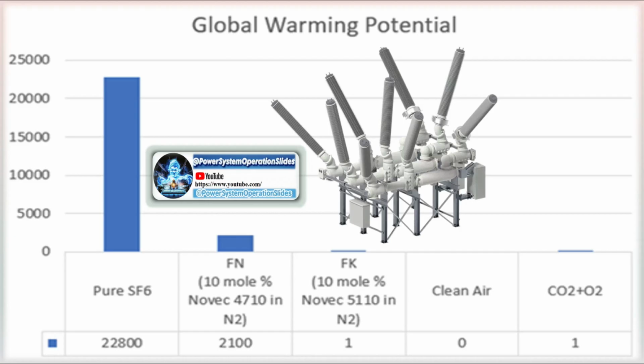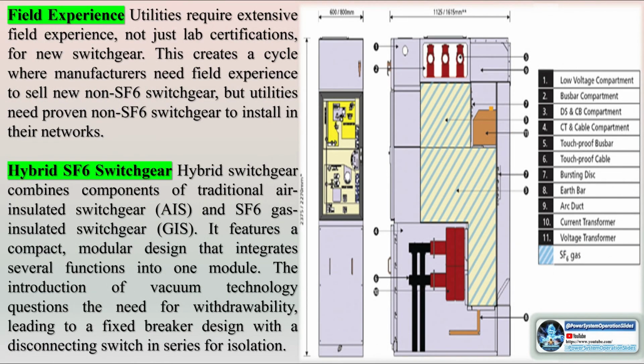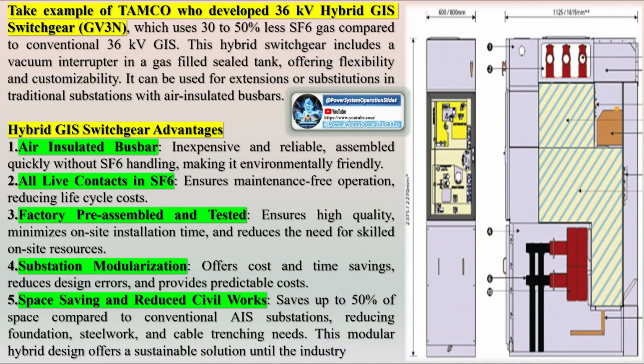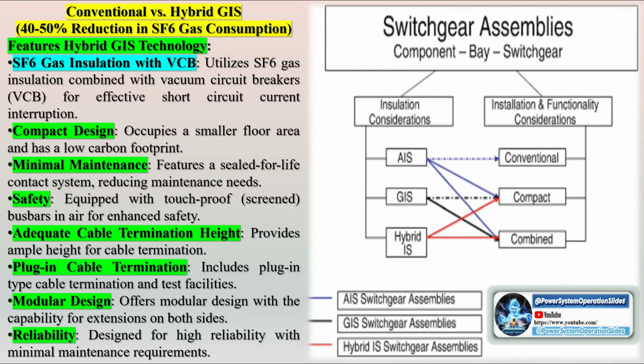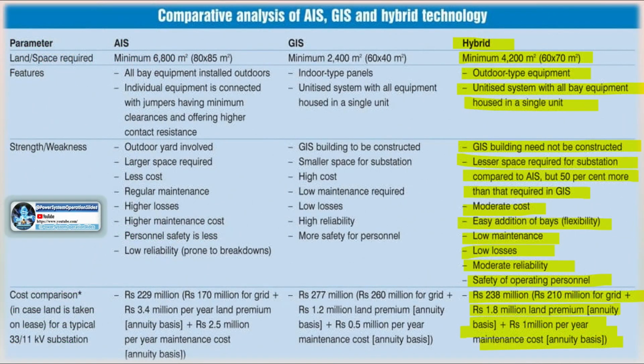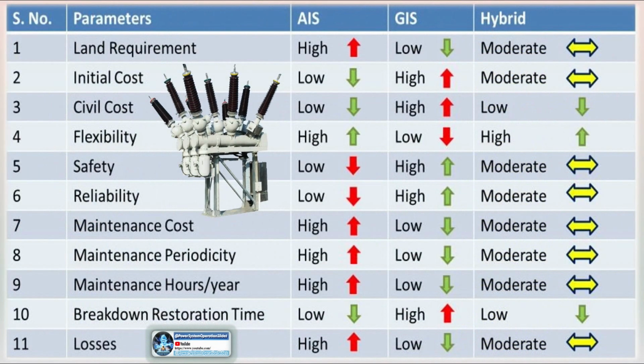Common failures: GIS can fail due to SF6 gas leaks, excessive microwater in the gas, or component failures. Regular testing and maintenance are crucial to ensure safe and reliable operation. Users need a maintenance checklist to prevent failures, optimize performance, identify issues early, minimize outages, and extend lifespan. Annual checks and condition inspections every 5 to 10 years include voltage withstand tests, contact resistance, relay operation, and other parameter checks. Components are usually lubricated for life, but occasional oiling may be needed after many years. Maintenance may involve breaker replacement, SF6 gas removal or recharge, and other updates. Manufacturers provide specific maintenance guidelines, including frequency and procedures, ensuring the switchgear remains in good condition.